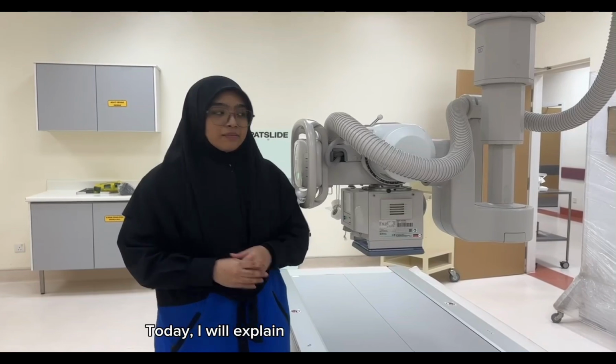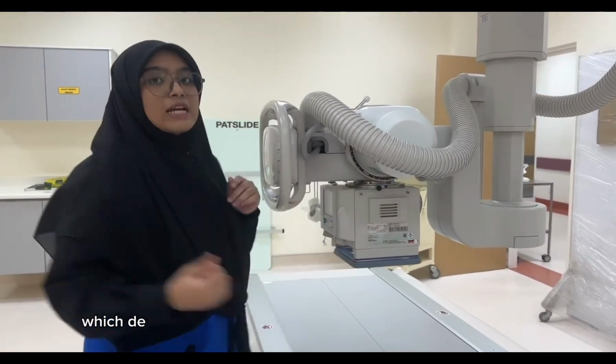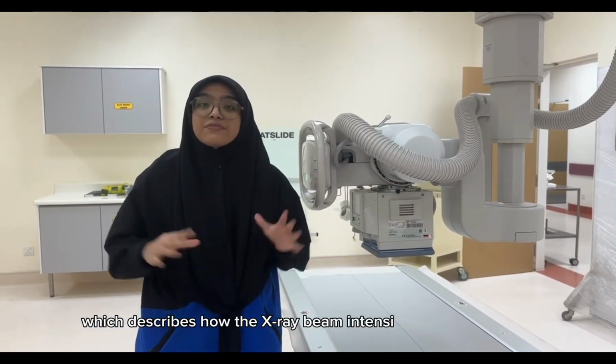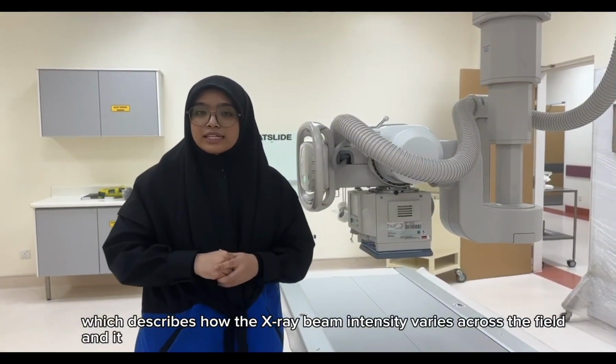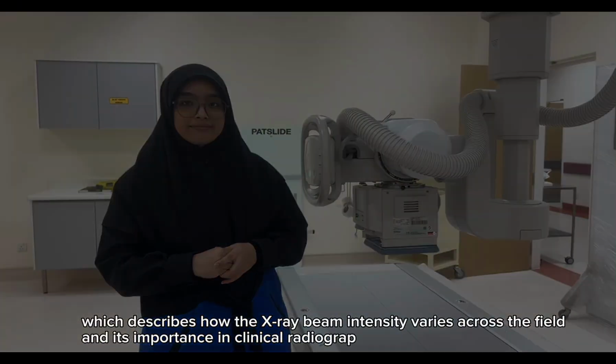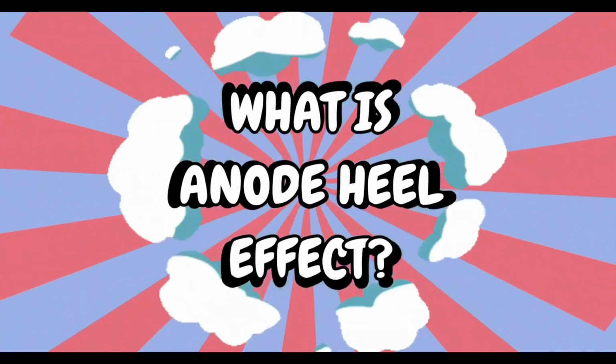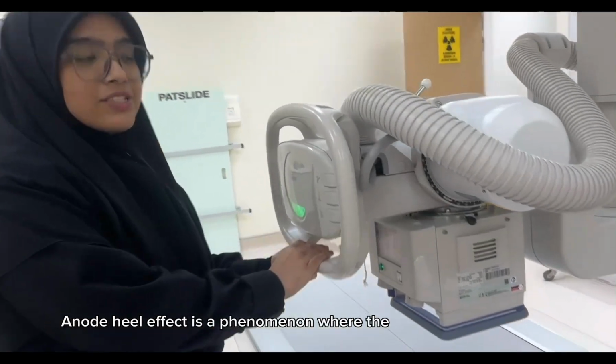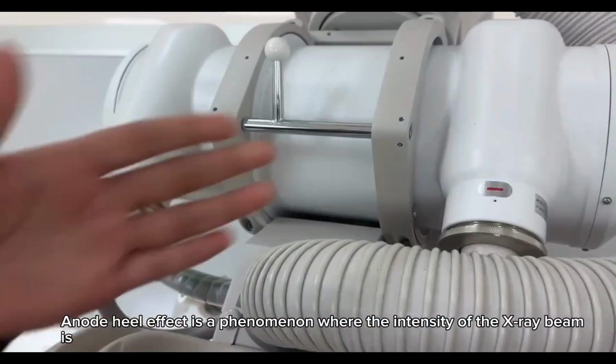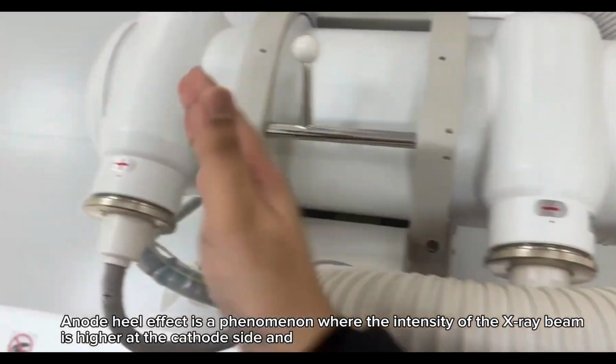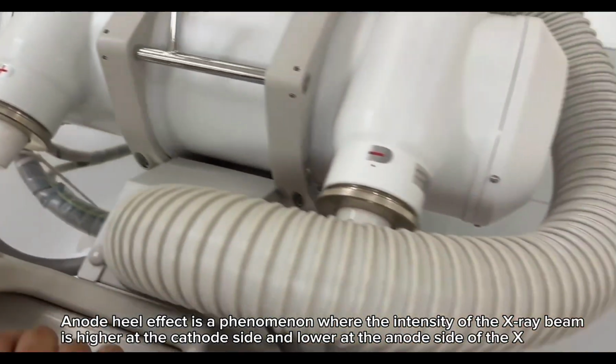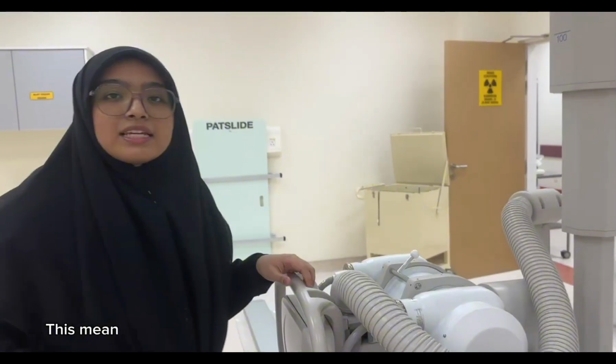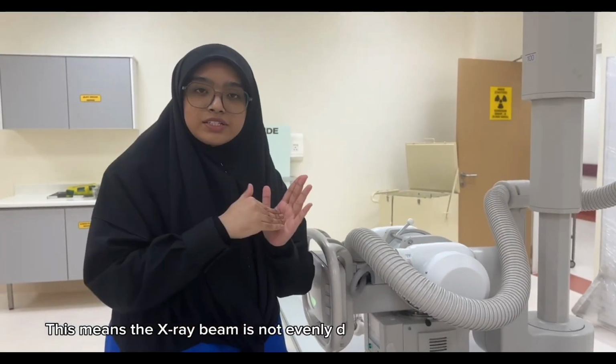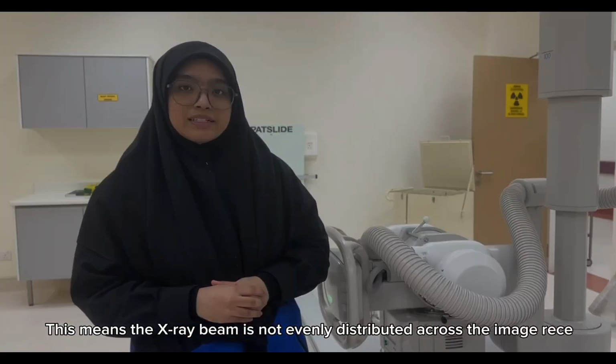Today I will explain about the anode heel effect, which describes how the X-ray beam intensity varies across the field and its importance in clinical radiography. What is the anode heel effect? The anode heel effect is a phenomenon where the X-ray beam intensity is higher at the cathode side and lower at the anode side of the X-ray tube. This means the X-ray beam is not evenly distributed across the image receptor.